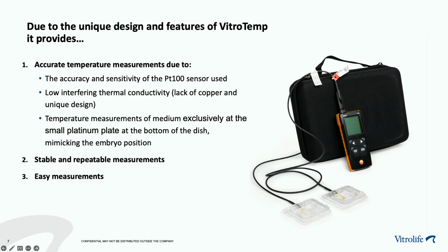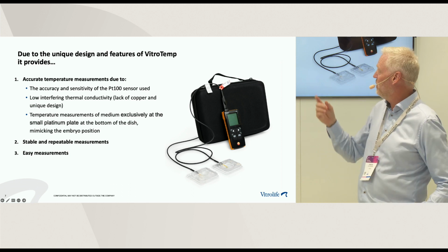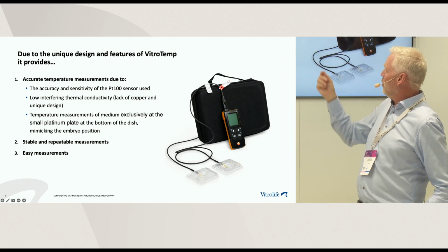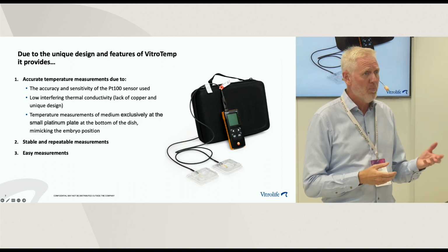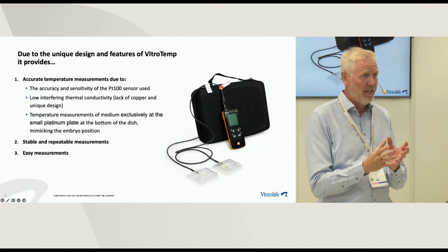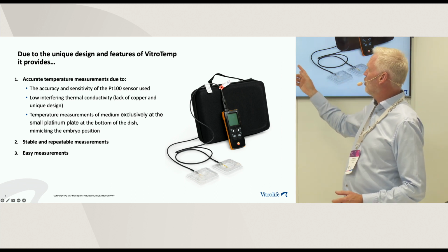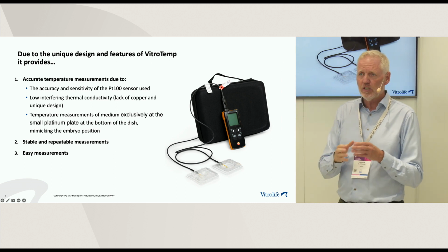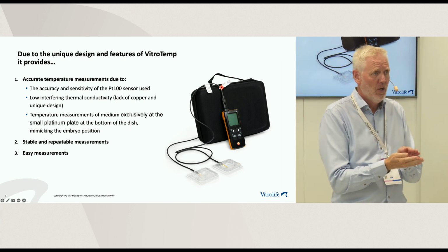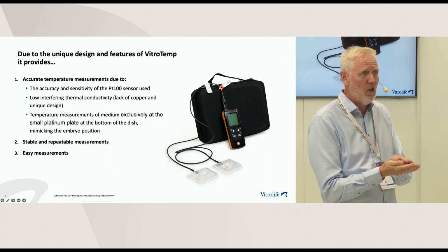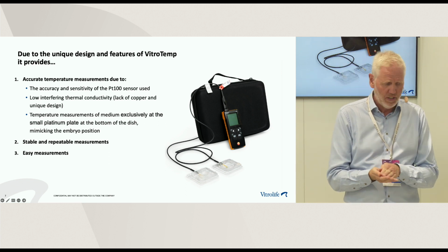Accurate measurement might be the most important, and you get that due to, one, the accuracy and the sensitivity of the probe itself, because a PT100 has a higher accuracy and a higher sensitivity. Two, the low interfering thermal conductivity due to the lack of copper, due to the design of the dish. And the third thing that makes it correct is that you actually measure exclusively at the bottom of the dish where the embryos are supposed to be. So it mimics a normal culture condition.